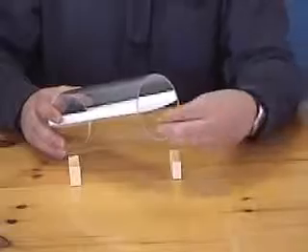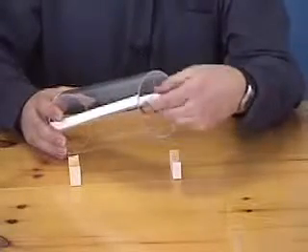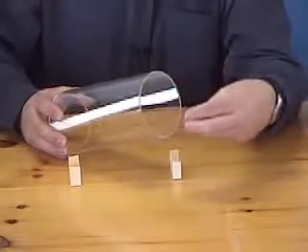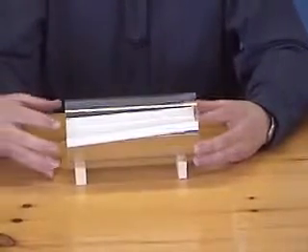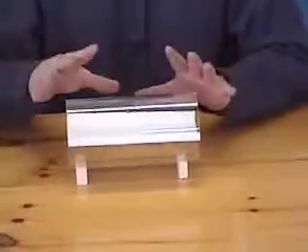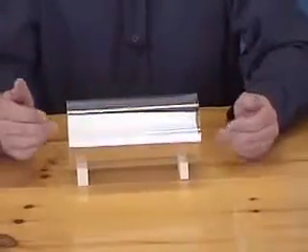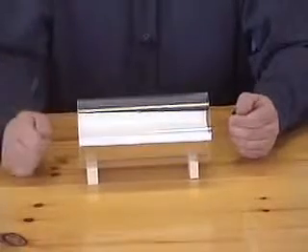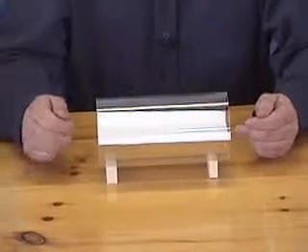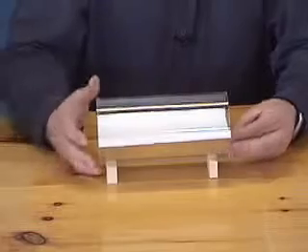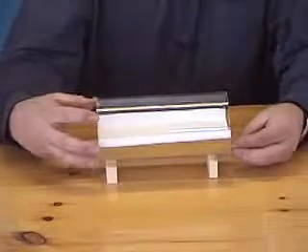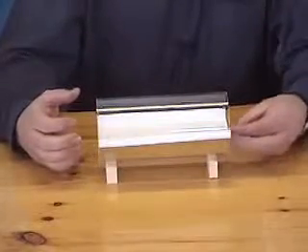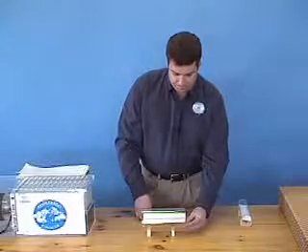When you come out the other end of this long imaginary tube, the air on the plastic side will be dry, and it will be close to the wet bulb temperature of the entering airstream. This is indirect evaporative cooling. It is both a heat and a mass exchange process. So in theory, the conditioned air you get at the end of this long pipe is going to be about half the quantity of the air you started with, and it will be cooled to the wet bulb temperature without adding any moisture.